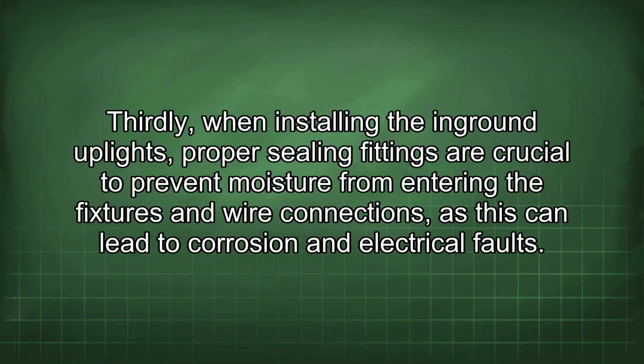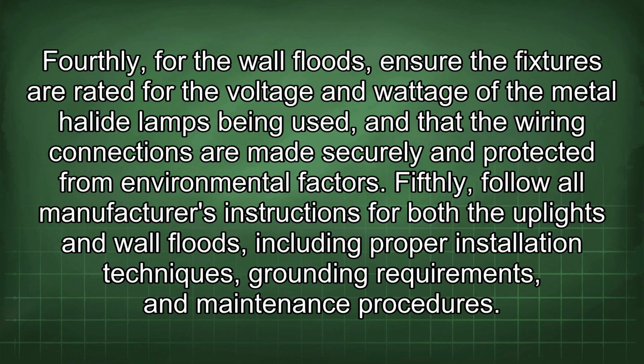Thirdly, when installing the in-ground uplights, proper sealing fittings are crucial to prevent moisture from entering the fixtures and wire connections, as this can lead to corrosion and electrical faults. Fourthly, for the wall floods, ensure the fixtures are rated for the voltage and wattage of the metal halide lamps being used, and that the wiring connections are made securely and protected from environmental factors.